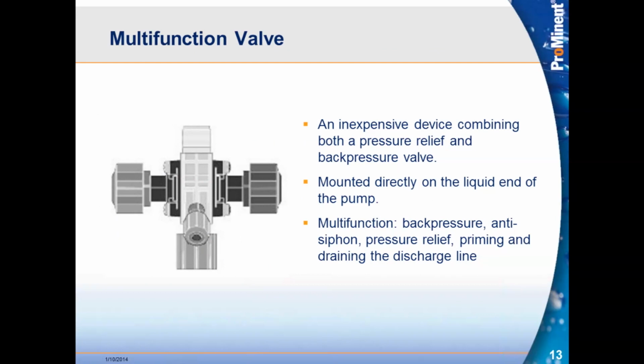We talked about back pressure, pressure relief. Those can be provided by the multifunction valve as well. The back pressure that the multifunction valve provides is fixed and it's pretty minimal. It's only 22 psi, where a typical back pressure or pressure relief valve, those are both adjustable up to about 150 psi. We can even get ones that are adjustable higher than that, but the most common ones are up to about 150 psi. So the back pressure is fixed on the multifunction valve. The pressure relief is fixed as well, but there is a variety. The back pressure is 21 psi typically, and for the pressure relief, there are a couple of different levels depending on which pump and which range of pressure relief we wanted to include with them.